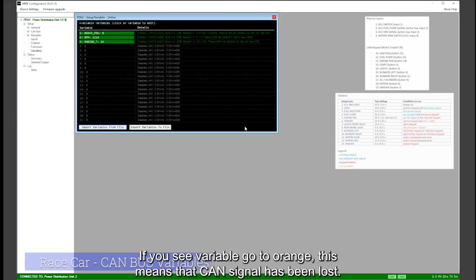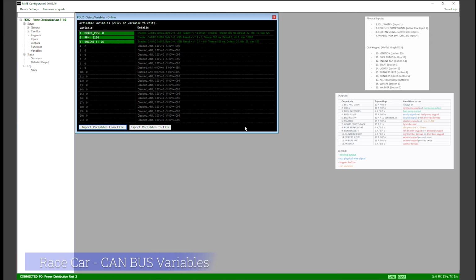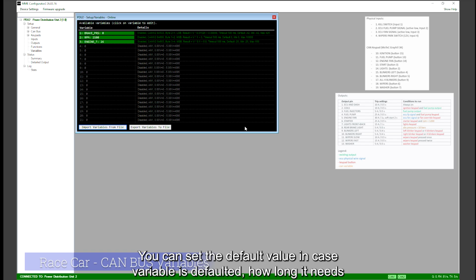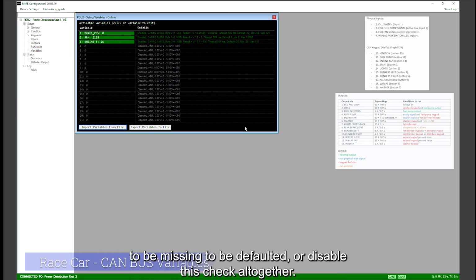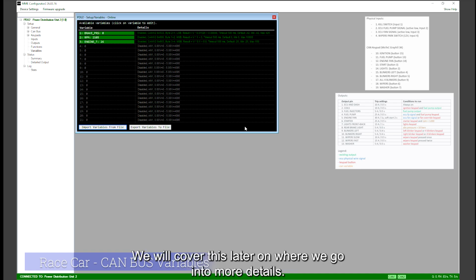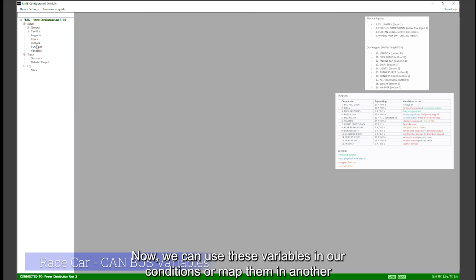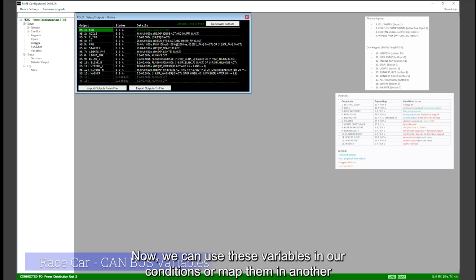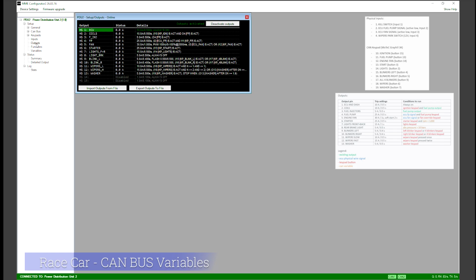Variables should light green, and we should see the values changing. If you see variable go to orange, this means that CAN signal has been lost. You can set the default value in case variable is defaulted, how long it needs to be missing to be defaulted, or disable this check altogether. We will cover this later on, where we go into more details. Now we can use these variables in our conditions or map them in another variable. Let's update our outputs now.